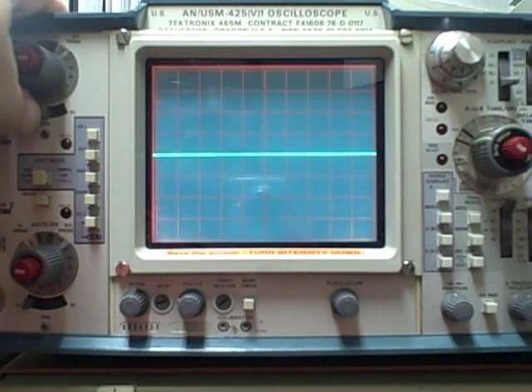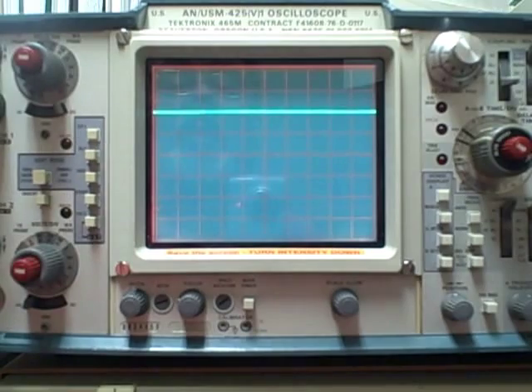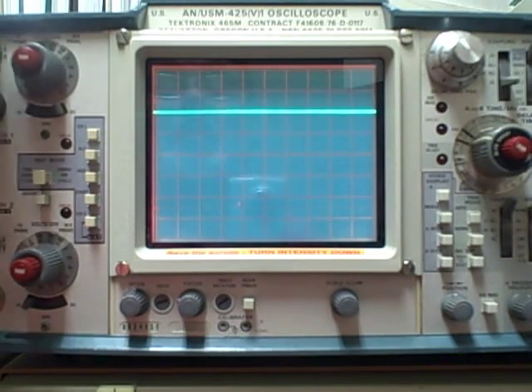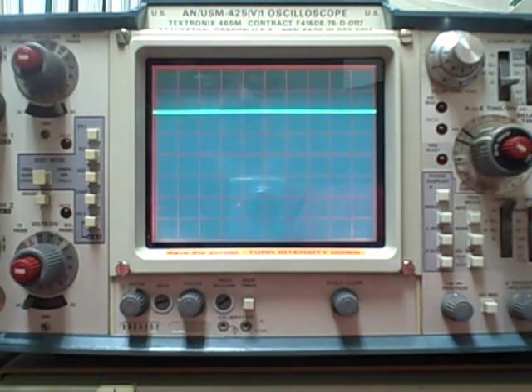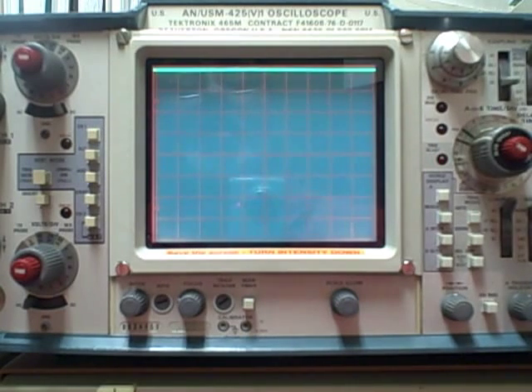There's our center graticule. We have 4 divisions up and 4 divisions down. Right now we are exactly 2 divisions up, and that would be 10 millivolts. We have 10 millivolts coming into the unit, so that is correct. So let's go ahead and double that. We should see ourselves go full scale. And that's exactly what we did. We're right on the line at the full scale mark.